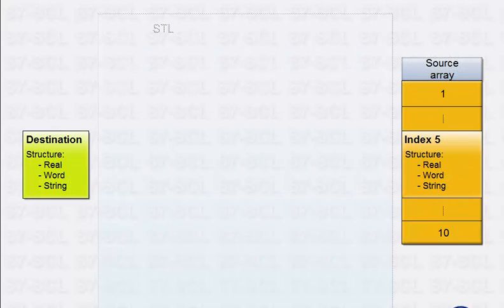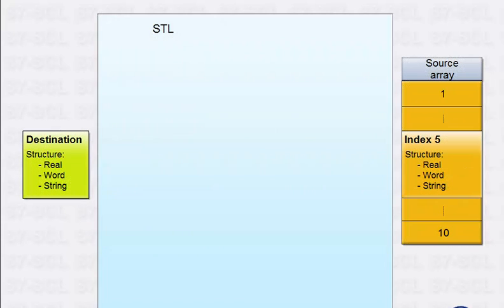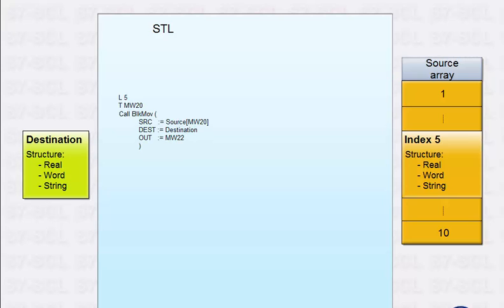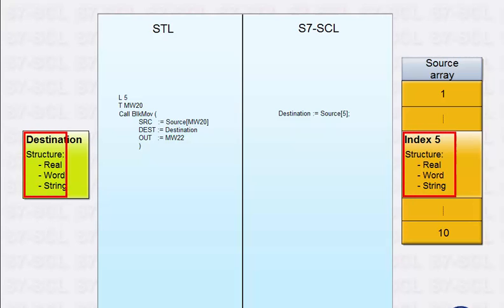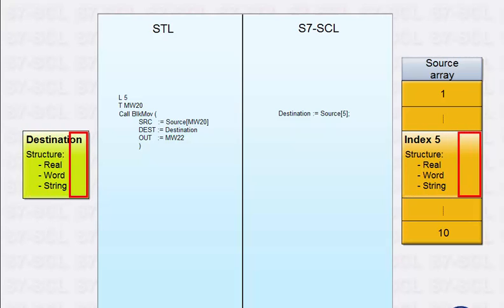In STL, such a task would require one block call and an index calculation via a memory word. With S7-SCL, you can realize this task with just one line, because S7-SCL has an index operator and an assignment operator. By using the assignment operator, you can copy complete structures with just one statement.